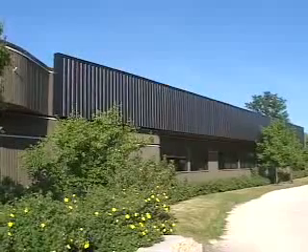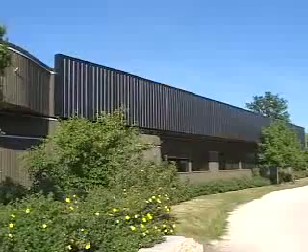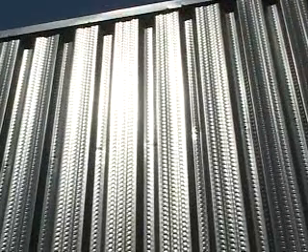From October to November, you get a temperature here on average of about minus 8 to minus 12 degrees. With this heating up, we can pretty much take this air and move it into the building without actually heating it. When you get into January and February, which in Manitoba is a very cool time of the year, when you get temperatures of minus 30, minus 40 degrees sometimes, we basically use probably half of what we did previous to heating up the air.